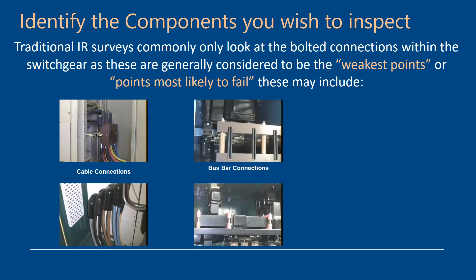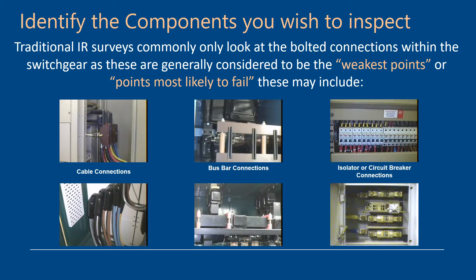First and foremost, you need to identify the components you wish to inspect within your panel. Traditional infrared surveys look at bolted or cable connections — what we class as the weakest connections within the panel. These include cable connections, bus bar connections, isolator or circuit breaker connections, and racking breakers. Faults tend to occur at the ends of joints where components are bolted together and where high-resistance connections can form. This is where we see failures and where we need to concentrate when putting in inspection systems.